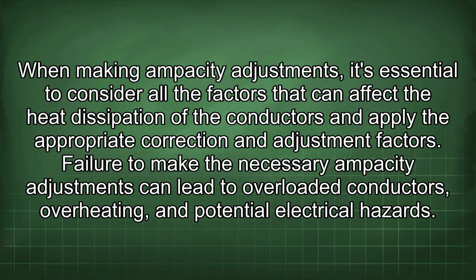When making ampacity adjustments, it's essential to consider all the factors that can affect the heat dissipation of the conductors and apply the appropriate correction and adjustment factors. Failure to make the necessary ampacity adjustments can lead to overloaded conductors, overheating, and potential electrical hazards.